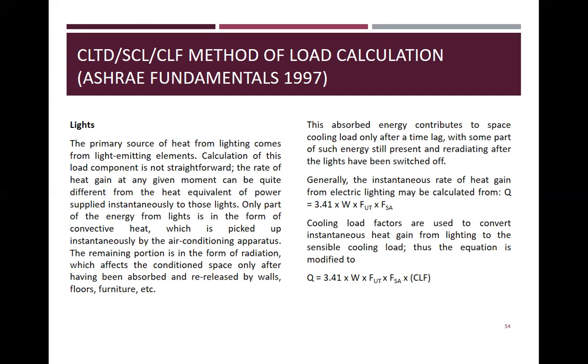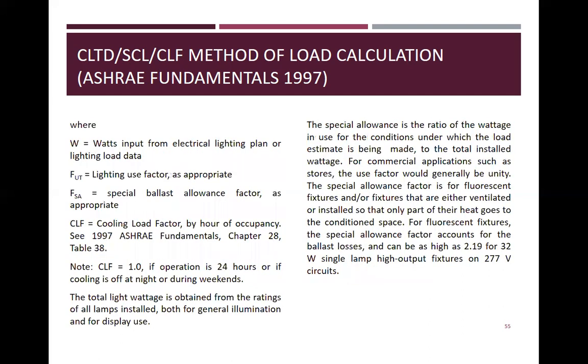Generally, the instantaneous rate of heat gain from electric lighting may be calculated from Q = 3.41 × W × FUT × FSA. Cooling load, mamaya yung symbols. Cooling load factors are used to convert instantaneous heat gain from lighting to sensible cooling load. Thus, the equation is modified to Q = 3.41 × W × FUT × FSA × CLF, where W is the watts input from electrical lighting plan or lighting load data. FUT is the lighting use factor as appropriate. FSA is the special allowance factor as appropriate. CLF is the cooling load factor by hour of occupancy. See 1997 ASHRAE Fundamentals chapter 28 table 38. Note CLF is equal to 1.0 if operation is 24 hours or if cooling is off at night or during weekend.